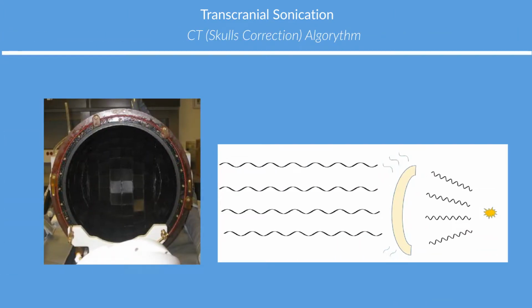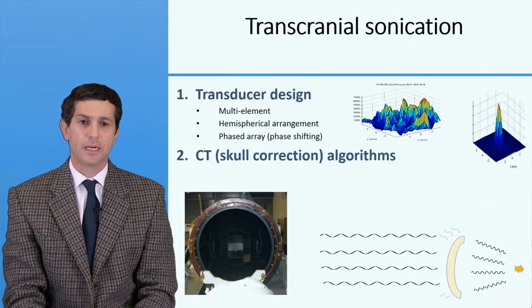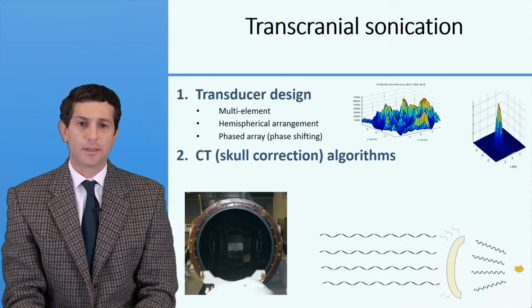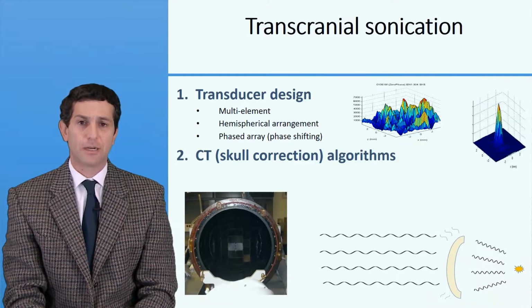There are now multi-element systems where our current clinical device uses 1024 elements which can be individually controlled and phase shifted so that ultrasound beams, as they transmit through the skull, can be really deflected or refracted to a focus. And the hemispherical arrangement of the transducer also adds to the ability to converge these ultrasound beams to a single focus.